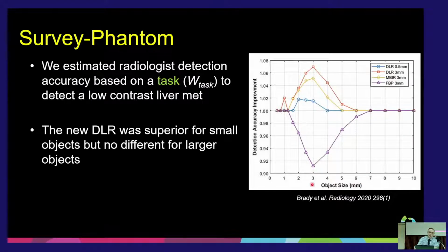And it's really, really good, gives us higher diagnostic confidence, better ability to see smaller objects. And we actually tested this for different contrast levels, subtle contrast differences of say 50 Hounsfield units all the way up to 300 Hounsfield units. The beautiful thing is you can see no matter if an object gets larger and larger, and I think our radiologists would agree, if you have a very big fat lesion, it doesn't matter how noisy the image is, you can probably see that lesion.